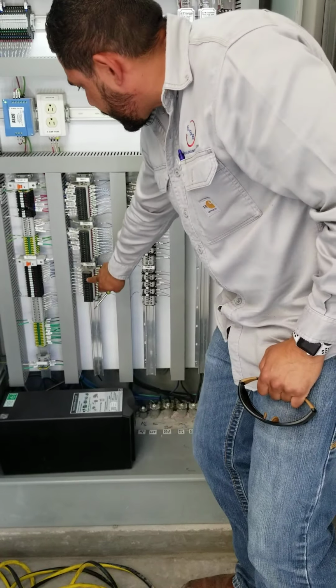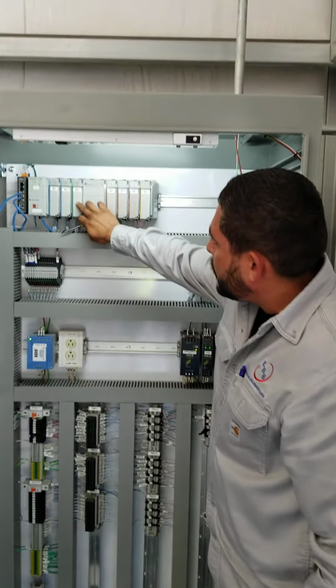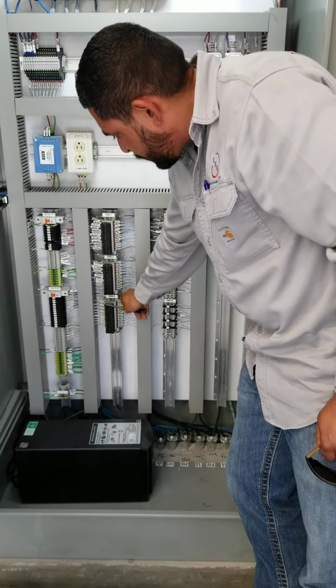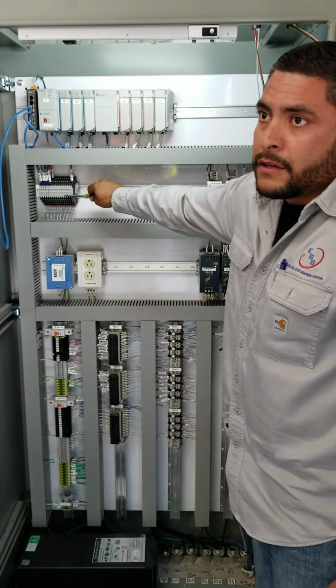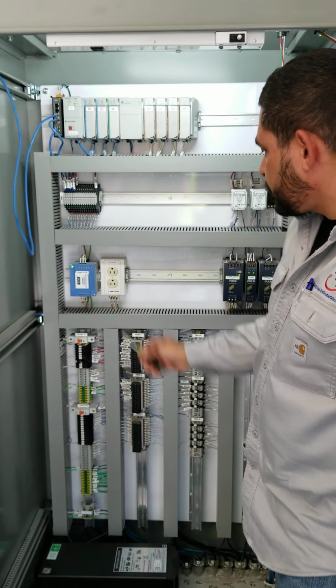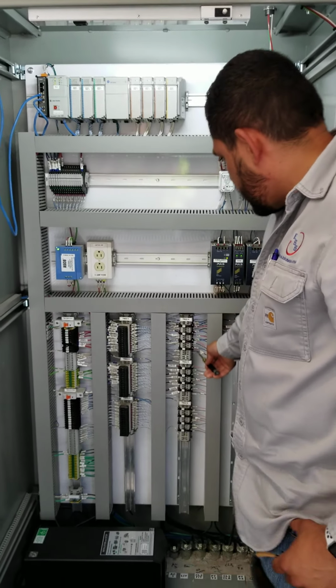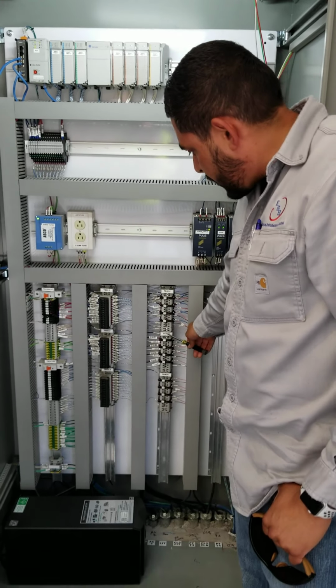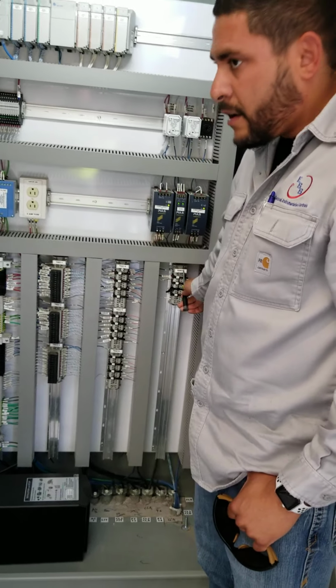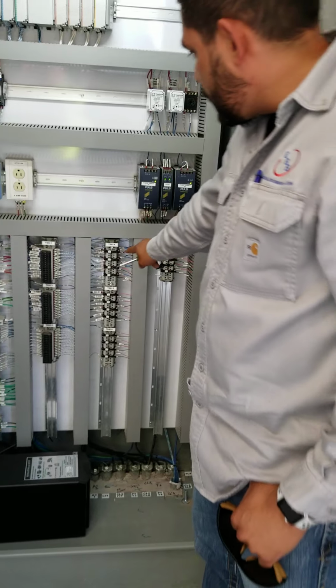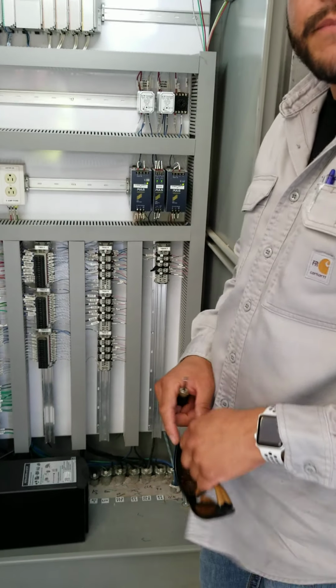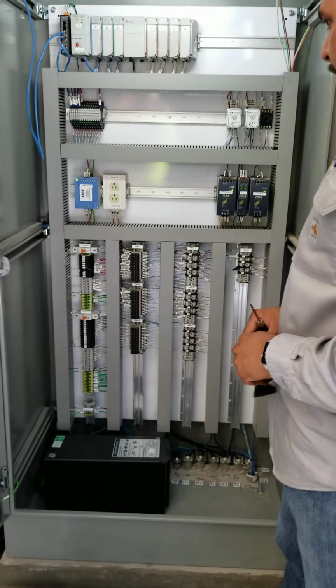All these are from here. It goes from the output of the PLC to this terminal block protection, and then from there it goes to our relays, solid state relays. And then this section is all your analog inputs, and this is your analog outputs. They're also fused. These are all your four to 20 milliamp signals, and that's pretty much it.